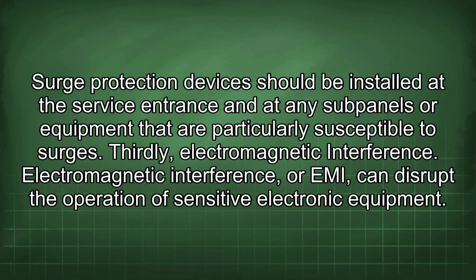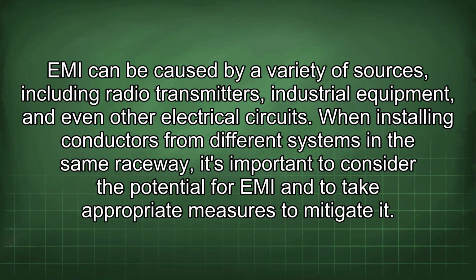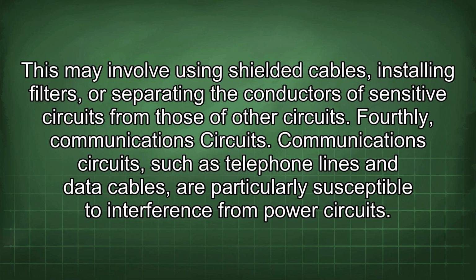Thirdly, electromagnetic interference. Electromagnetic interference, or EMI, can disrupt the operation of sensitive electronic equipment. EMI can be caused by a variety of sources, including radio transmitters, industrial equipment, and even other electrical circuits. When installing conductors from different systems in the same raceway, it's important to consider the potential for EMI and to take appropriate measures to mitigate it. This may involve using shielded cables, installing filters, or separating the conductors of sensitive circuits from those of other circuits.